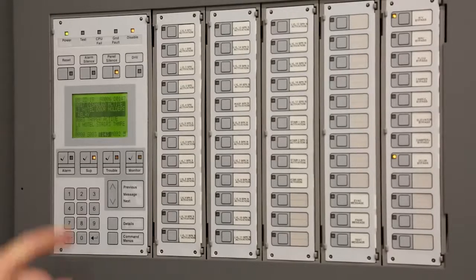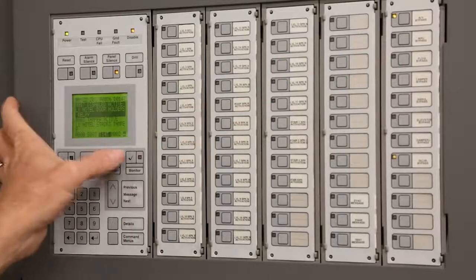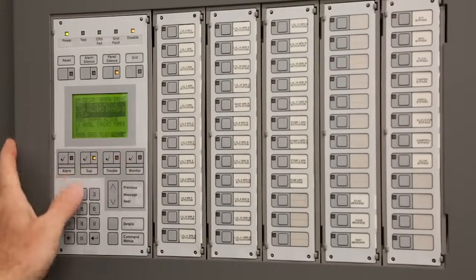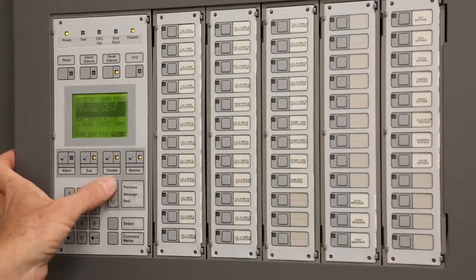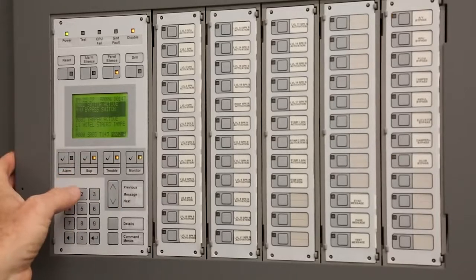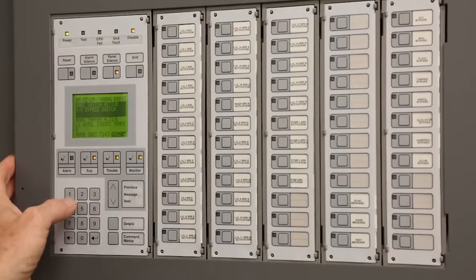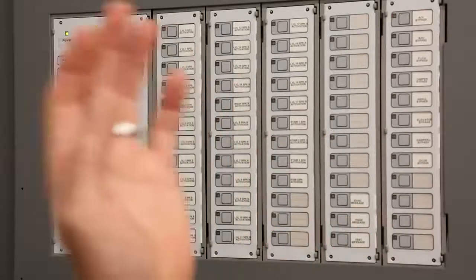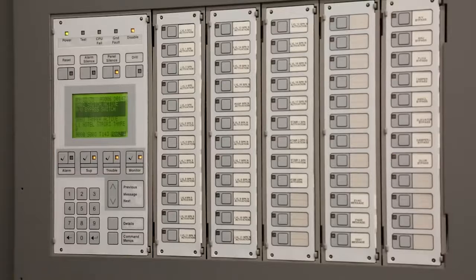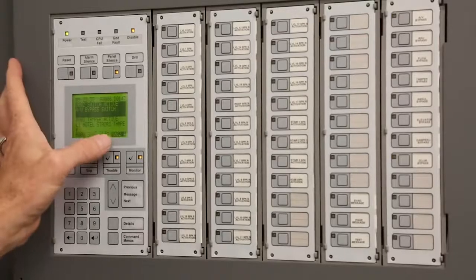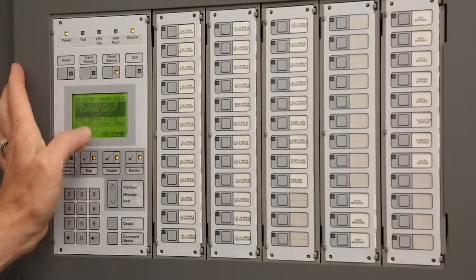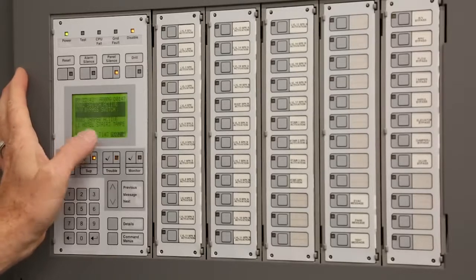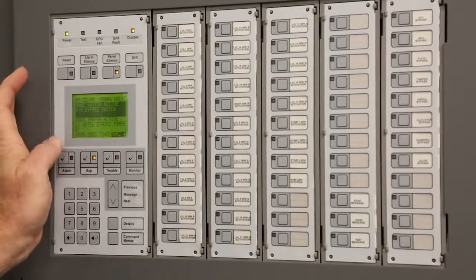Again, like I said, if I just push that other button right there, the monitor, if you notice, it went up to 2 points, and you can scroll up and down on that also, and it'll say AV bypass switch is activated, okay? So monitor points, like I said, are just switch actions, anything on the smoke control panel, any dampers. That does not report to the third party. The dialer does not report monitor points. It only reports troubles, supervisories, and alarms.